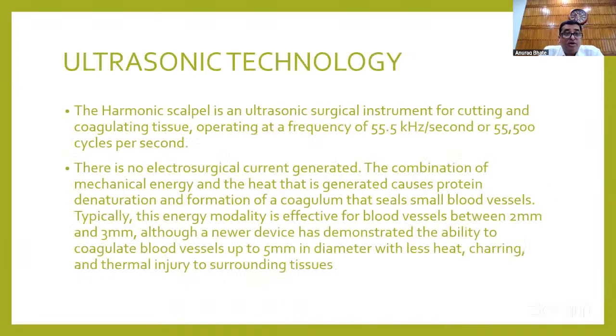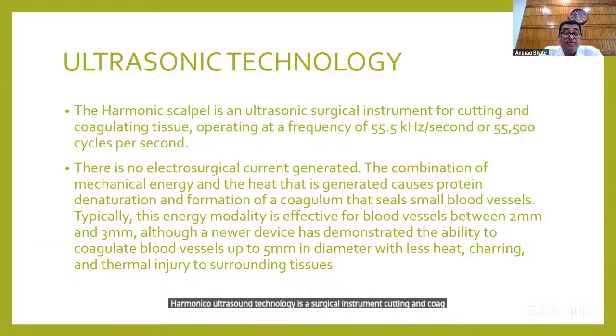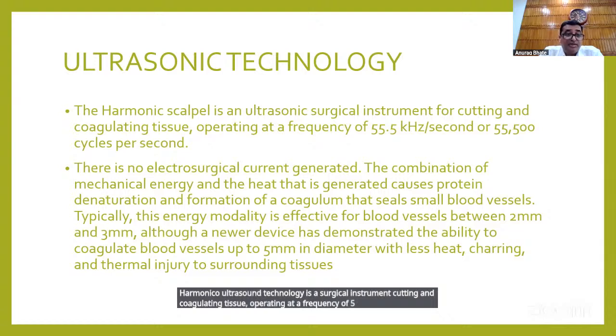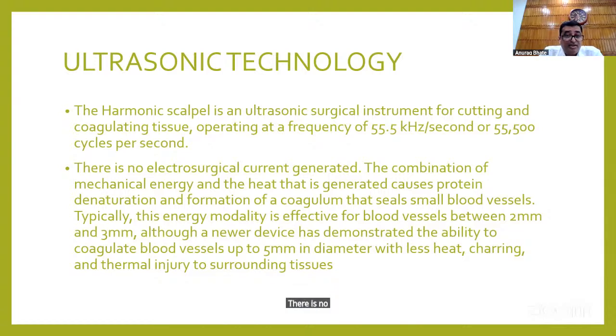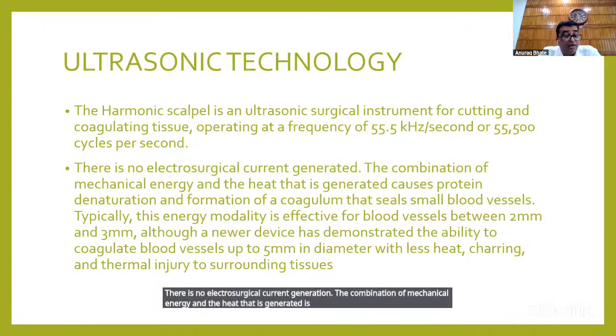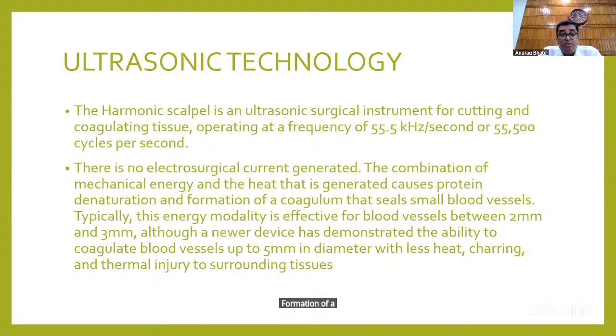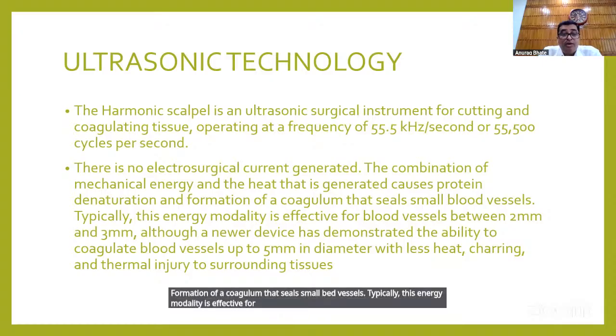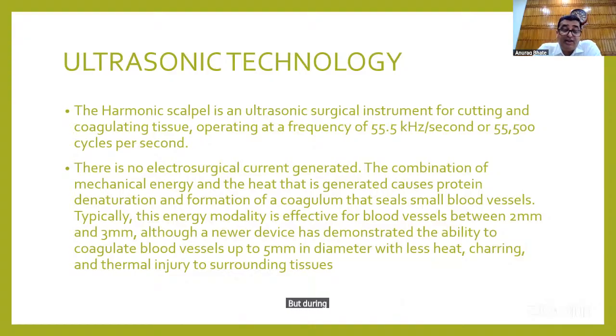Harmonic or ultrasound technology is a surgical instrument cutting and coagulating tissue, operating at a frequency of 55,500 cycles per second. There is no electrosurgical current generation. The combination of mechanical energy and the heat that is generated causes protein denaturation and formation of a coagulum that seals small blood vessels. Typically, this energy modality is effective for blood vessels between 2 and 3 millimeter, although a newer device is demonstrating ability to coagulate vessels up to 5 millimeter in diameter with less heat, charring, and thermal injury to the surrounding tissue. During bowel dissection, this is very, very useful because the thermal spread is very minimal.